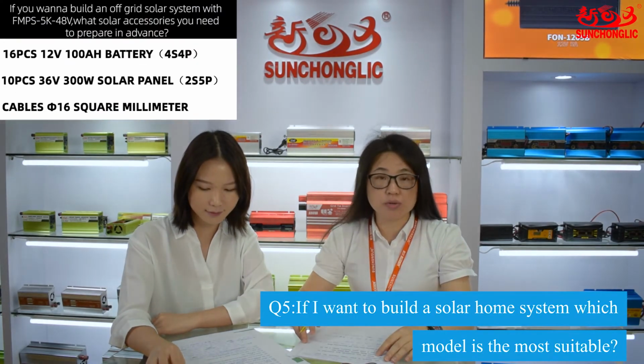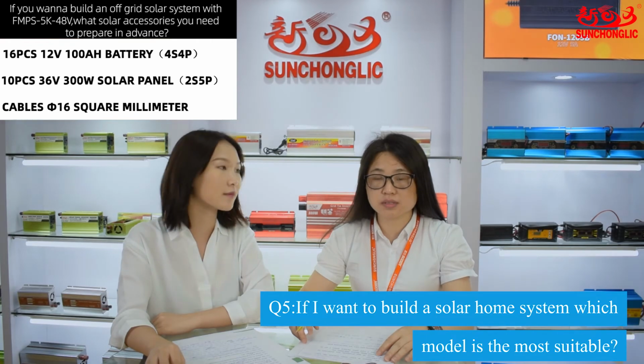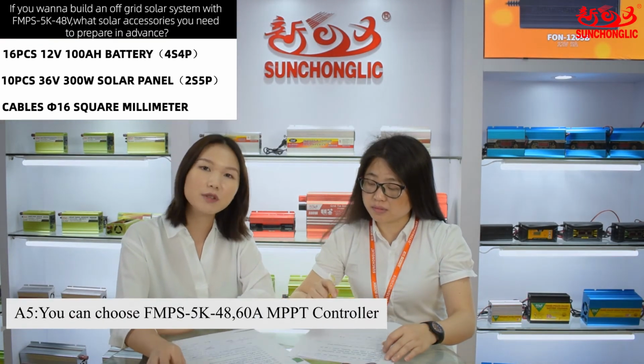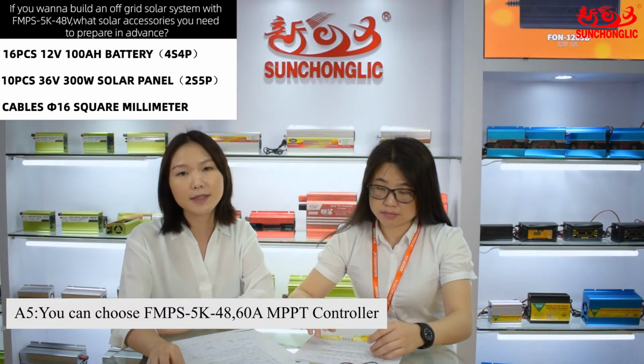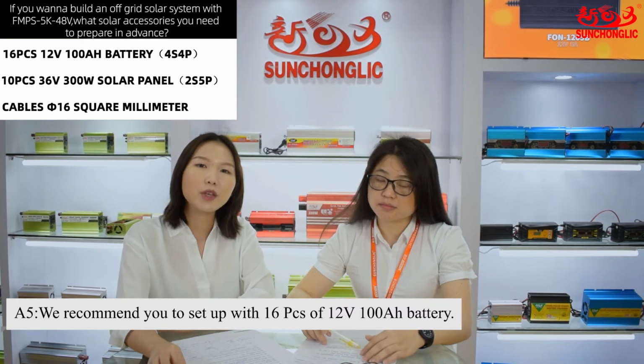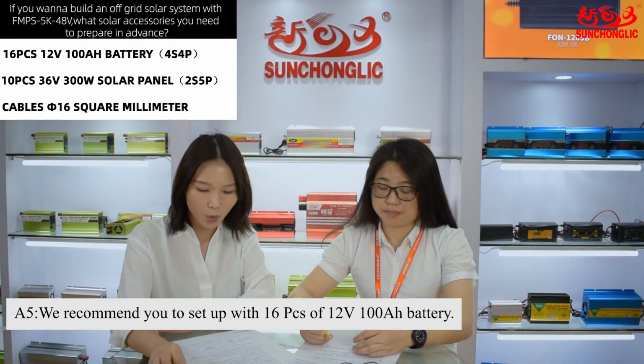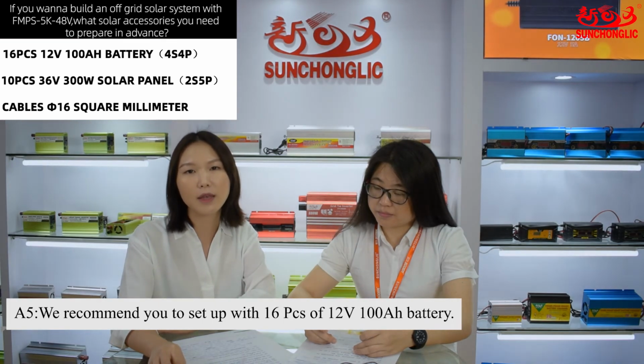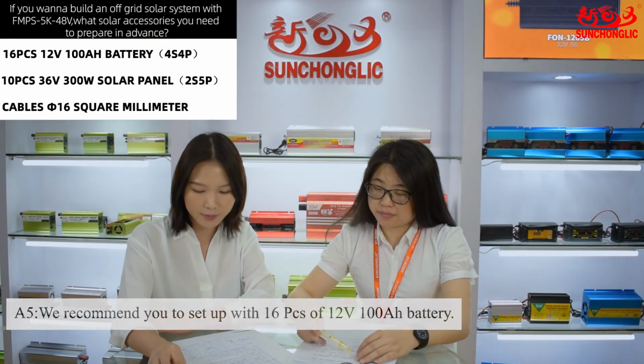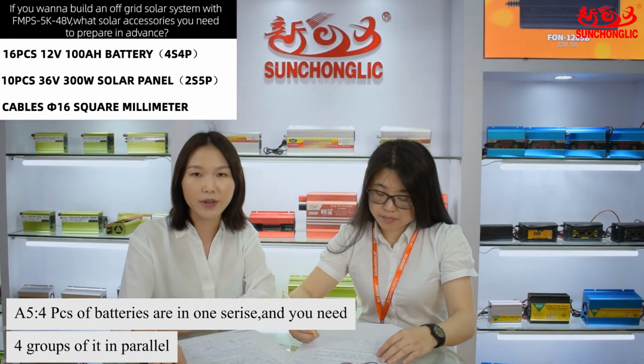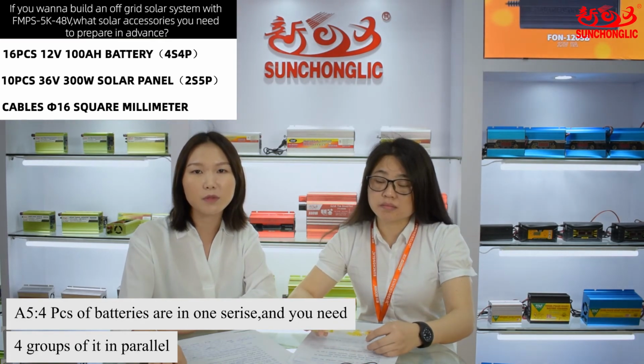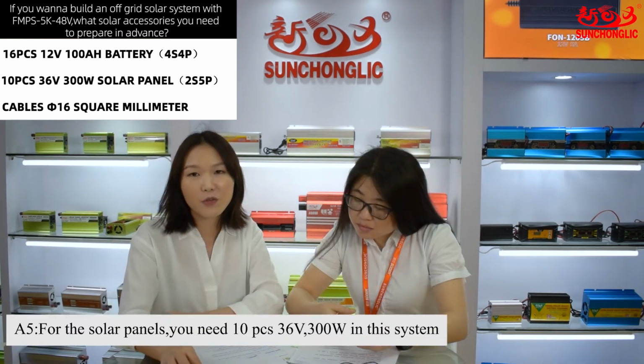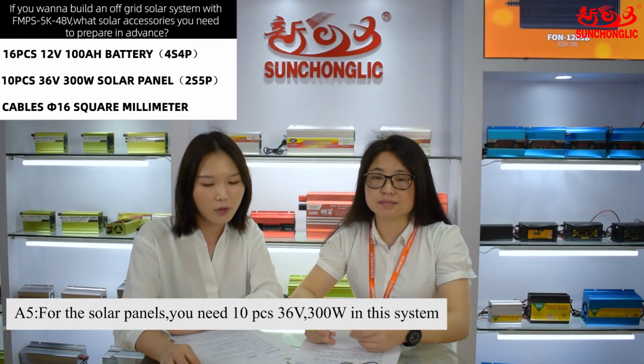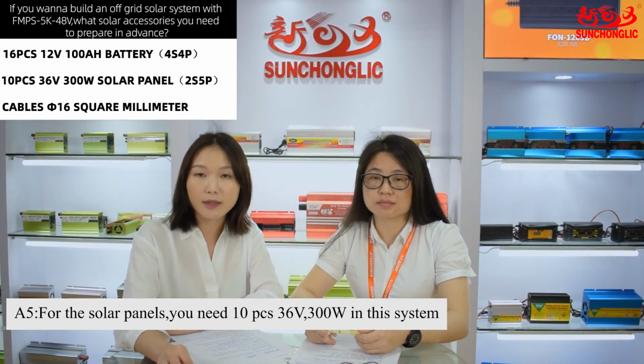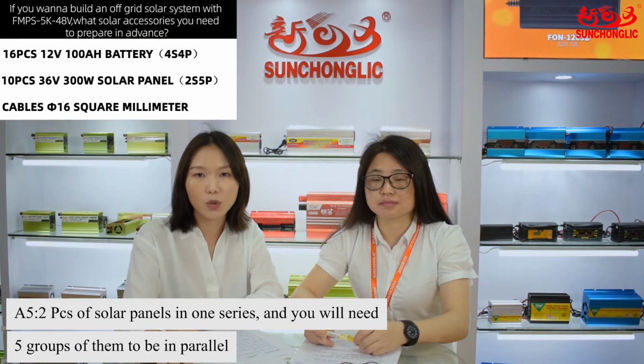If I want to build a solar home system, which model is most suitable? You can choose the FMPS 5K 48 volt with a 60 amp MPPT controller. We recommend setting up this solar home system with a total of 16 pieces of 12 volt 100 ampere-hour batteries, so you will need 4 pieces of battery in one series, and 4 groups of them in parallel. For the solar panels, you will need 10 pieces of 36 volt 300 watt panels in this system, 2 pieces of solar panels in one series, and 5 of those groups in parallel.